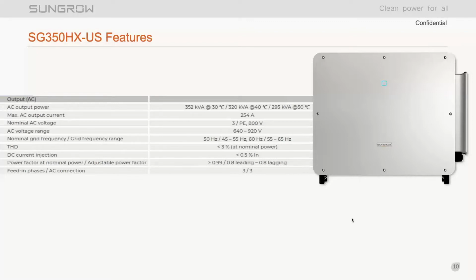We definitely meet the IEEE 1547 total harmonic distortion limits and the DC current injection, no problem there. And then the power factor: our reactive power curve is still the same as the 250, 0.8 leading and 0.8 lagging.